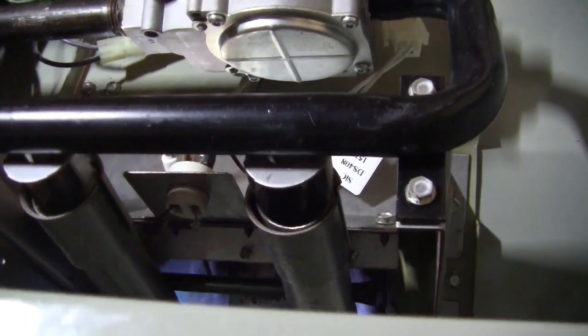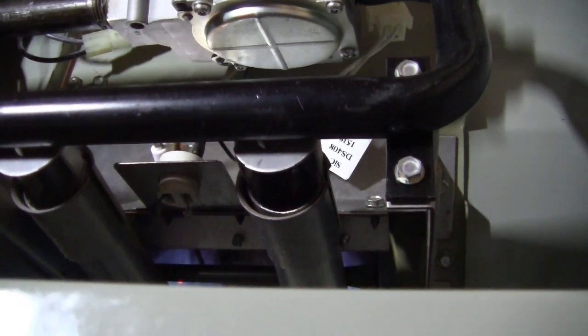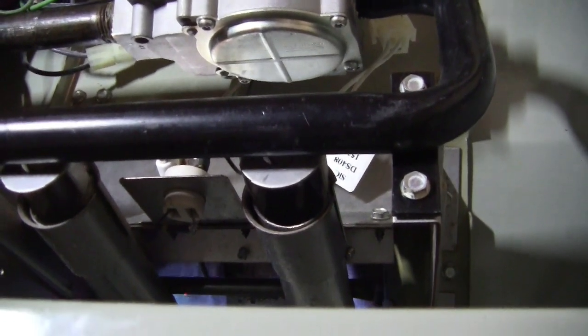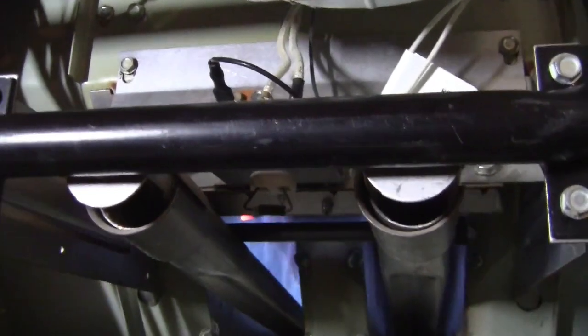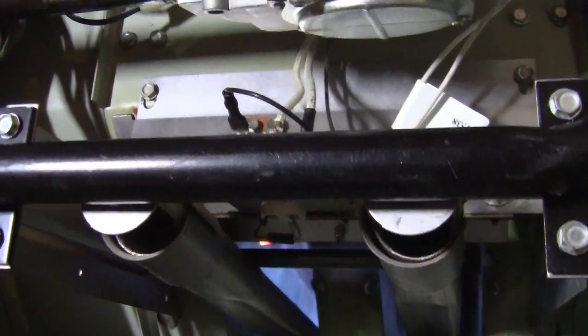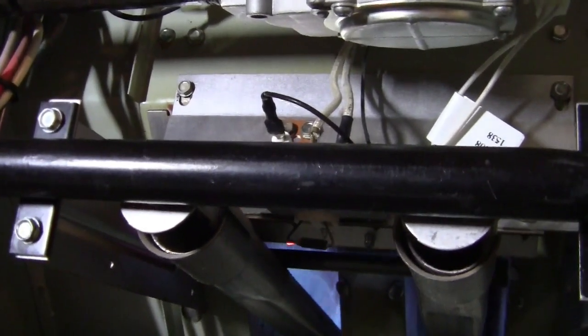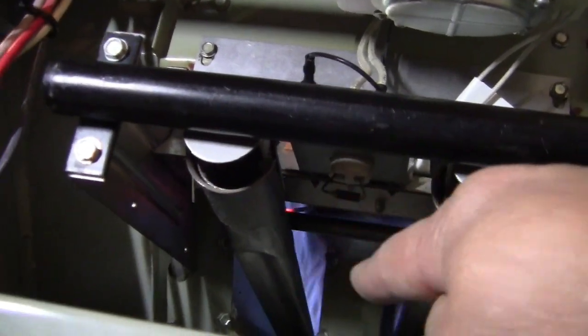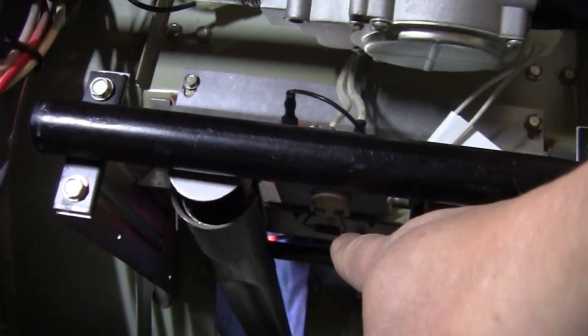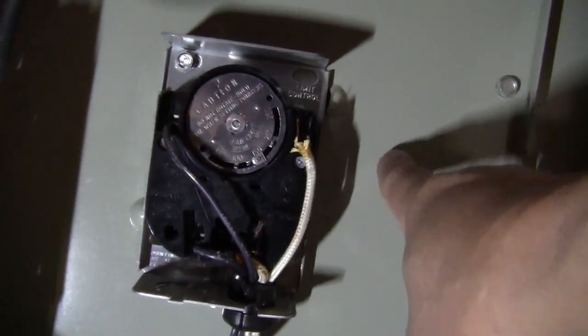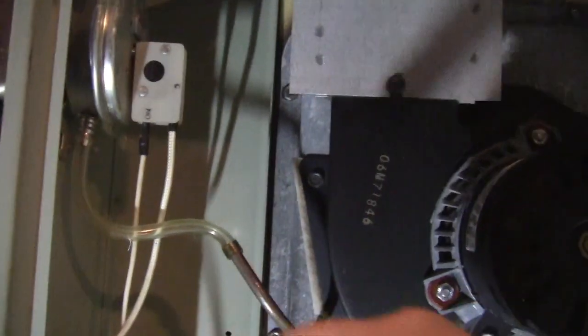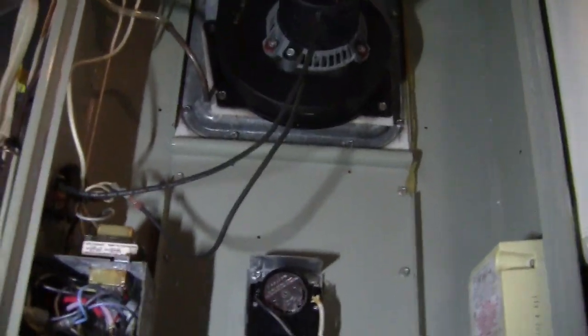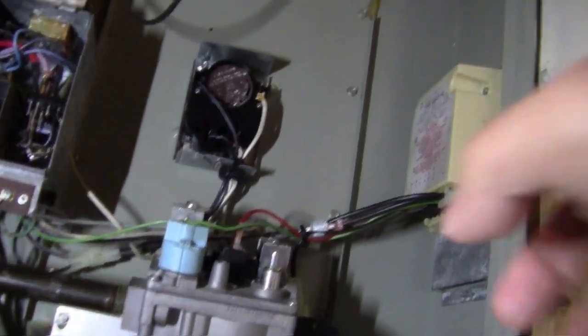So the flame sensor detects the fire and sends a signal to the controller, saying, I see the fire, so you can keep sending the gas. Yeah, see over there? The red hot stuff is the flame sensor, and this is the overflow sensor over here. If the fire comes out here, it's going to suck up the air, and if the air is not circulating, the temperature here is going to be very hot, and this guy is going to cut off the air. And this is the exhaust fan. If the exhaust fan is broken, there's no vacuum over here, and this guy is going to shut off everything. So the whole unit works, coordinated with each other, through this controller.